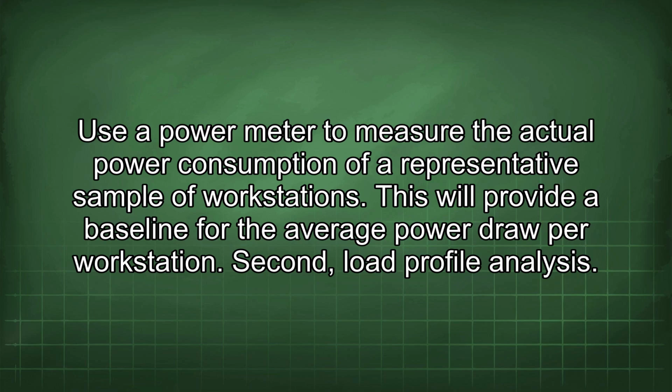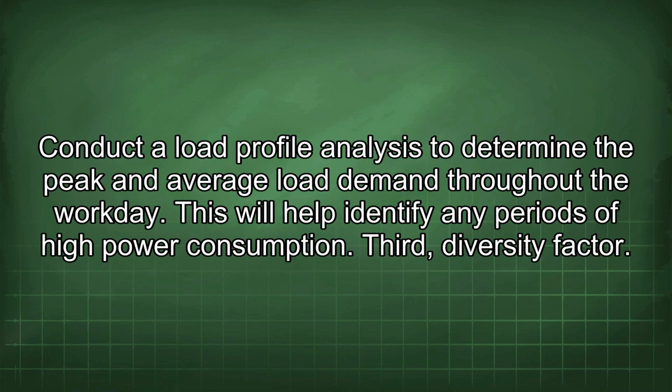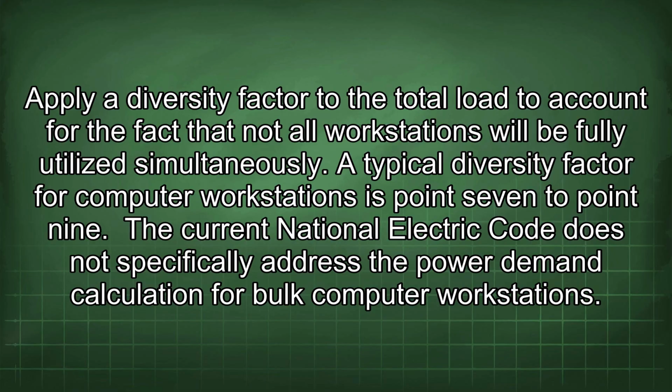Second, load profile analysis. Conduct a load profile analysis to determine the peak and average load demand throughout the workday. This will help identify any periods of high power consumption. Third, diversity factor. Apply a diversity factor to the total load to account for the fact that not all workstations will be fully utilized simultaneously. A typical diversity factor for computer workstations is 0.7 to 0.9.